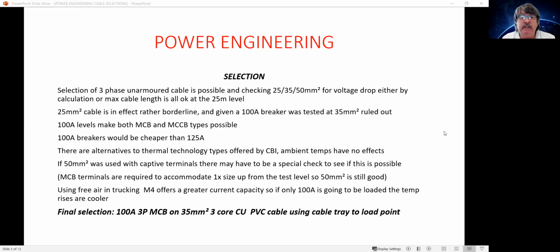So yeah, it's not as easy as we just did here. Obviously, I've looked at things like, as Andrew said, I'll probably go with a 3-core, 3-phase unarmored type of arrangement fitted on a cable tray of some sort. There are many trays, many versions out there. It offers quite a lot of latitude for higher temperatures and higher current. So there's good reserve on that cable for connection compromise. Yeah, 35mm typically in this case feeds the breaker size.